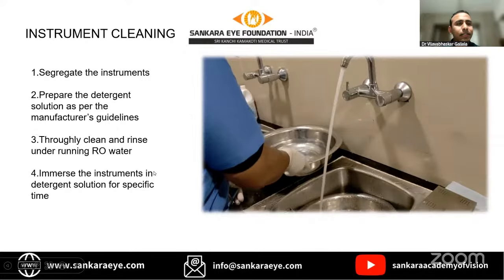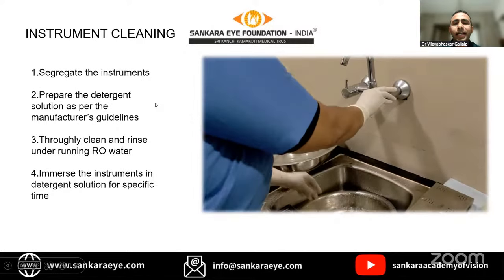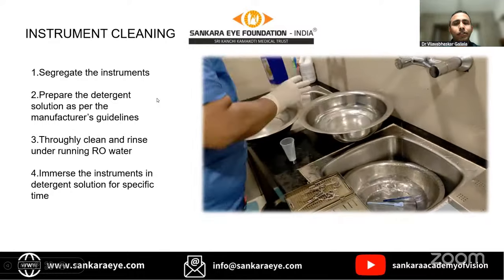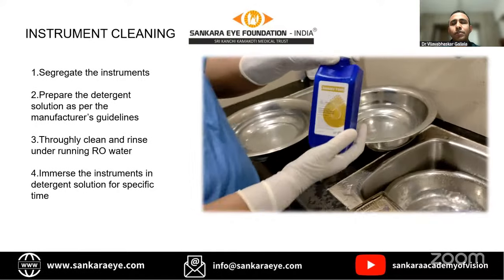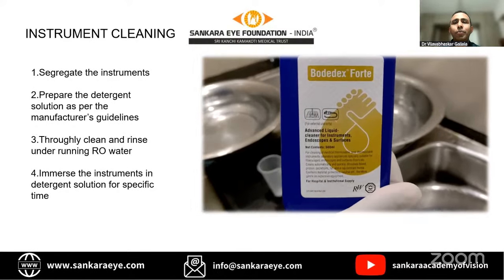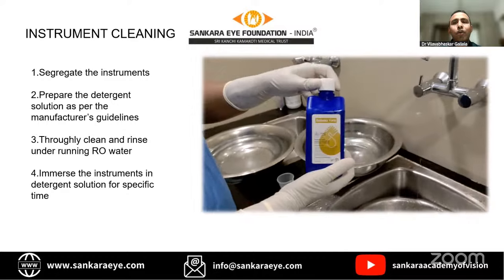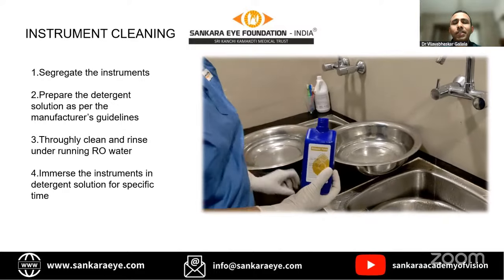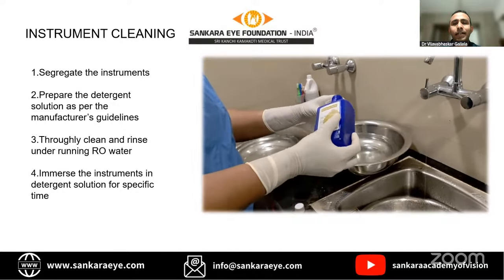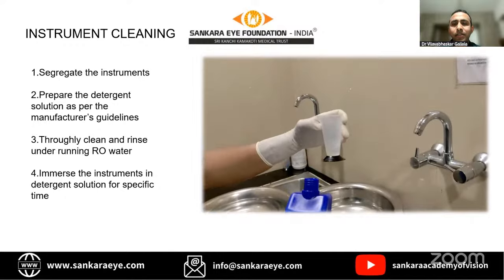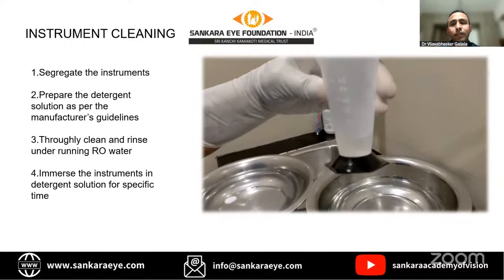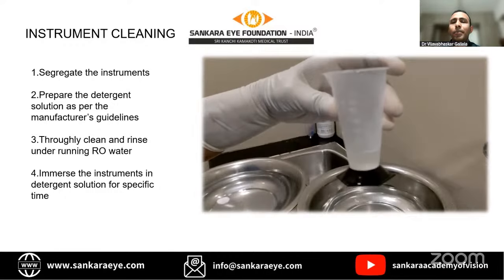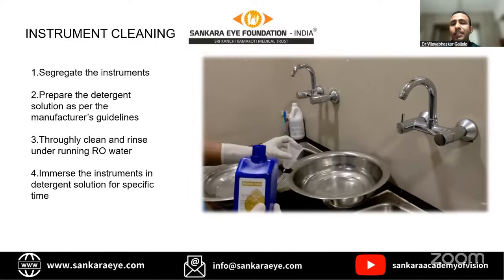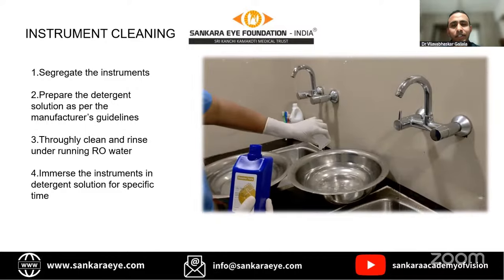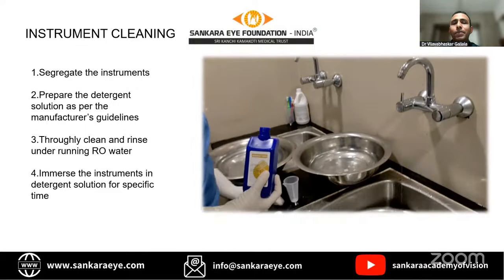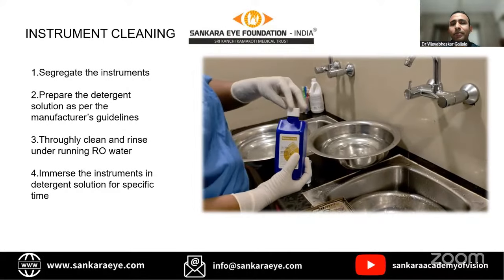The instrument cleaning. So first, segregate different types of instruments, like the sharp instruments and hollow instruments, into different bins. Then you prepare your neutral pH detergent, whatever the detergent that you are using. Please always follow the manufacturer guidelines. Whenever mixing this, please make sure that it should not be an estimated volume, it should be a measured volume. Because like 2 cups of detergent in 1 bin of water, it should not be like that. It's 5 ml or 10 ml. As per the manufacturer guidelines, you should measure and mix it.